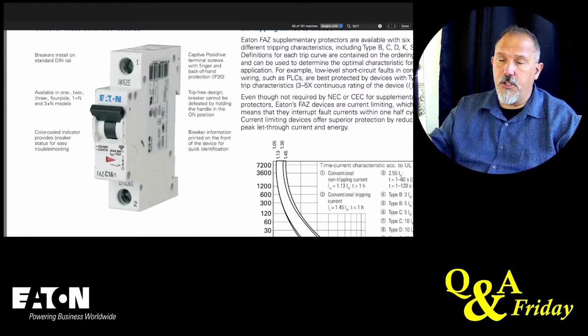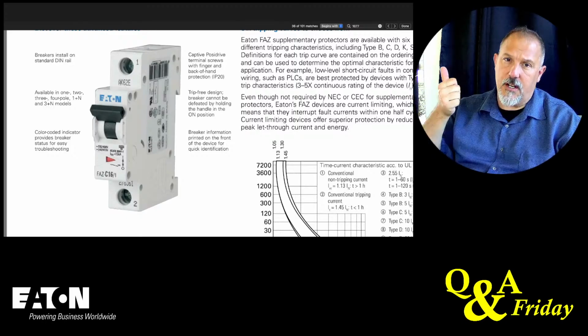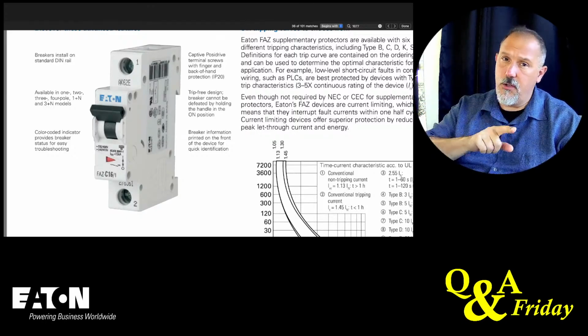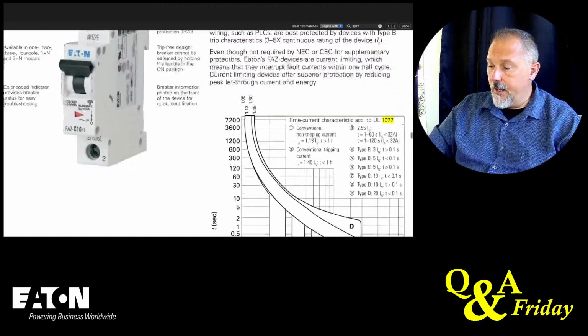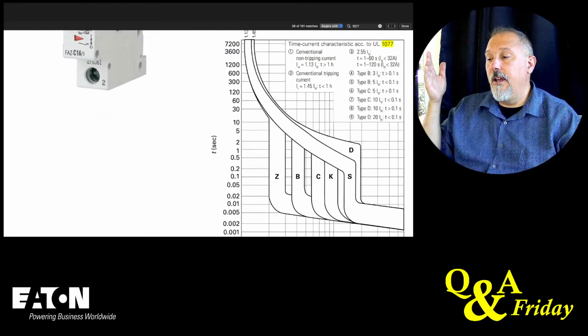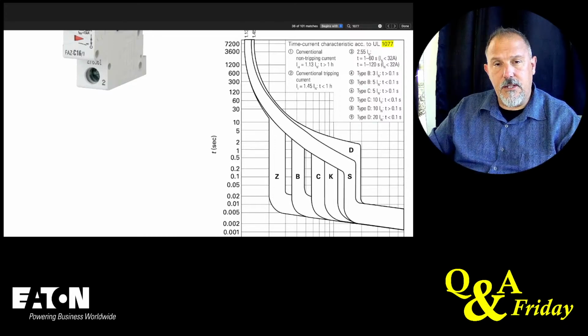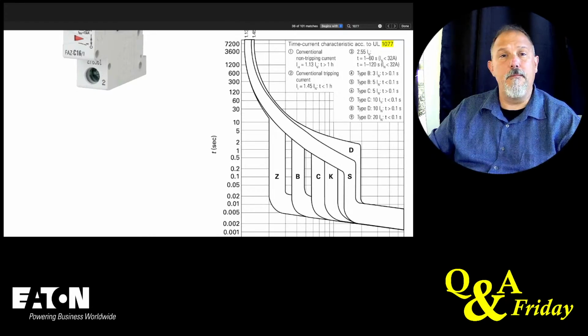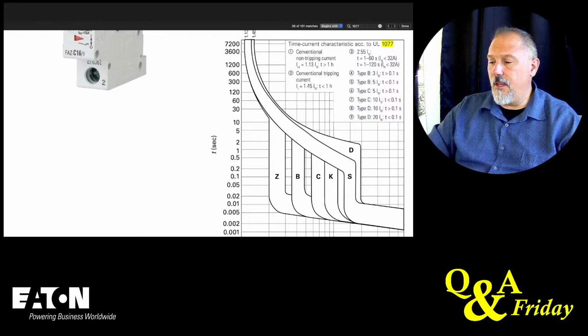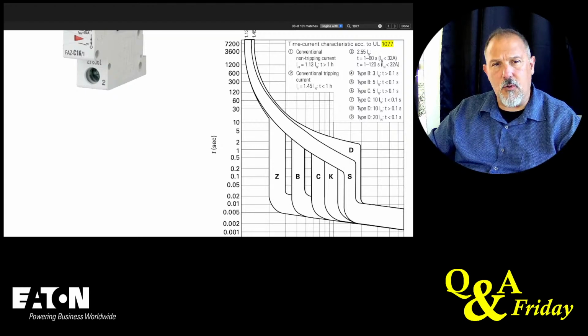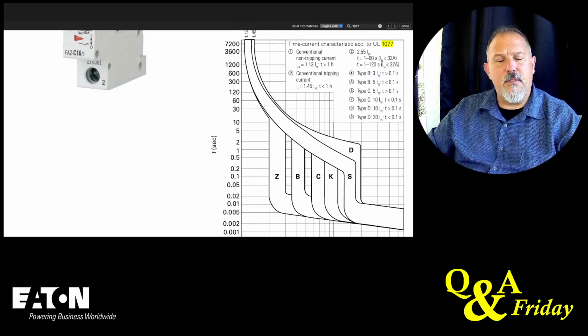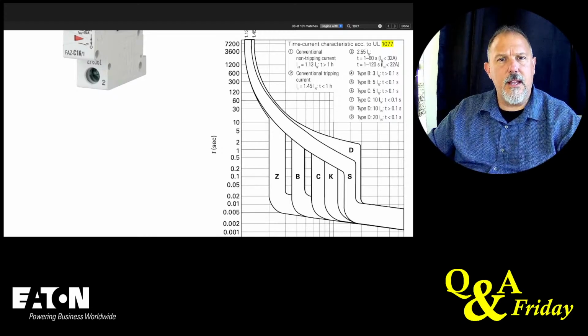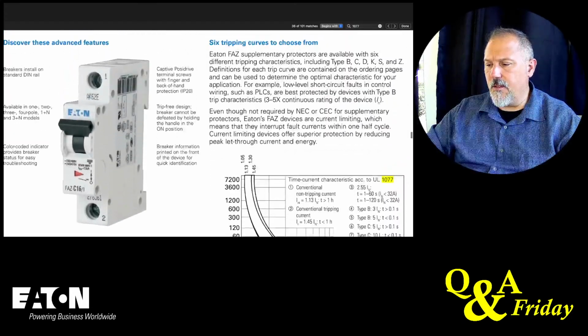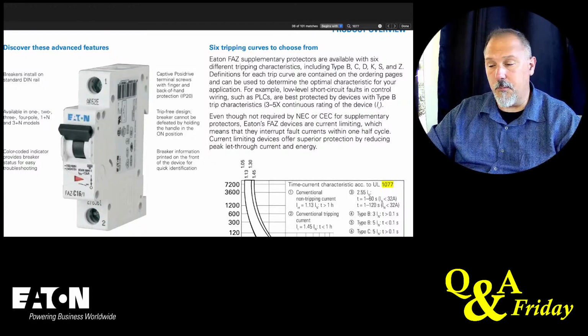Now, if I scroll back up in this document, you'll see a device that looks exactly like this, but it's UL 489, not a 1077. And to answer the specific question, it does have a thermal and it does have an instantaneous. They're just like a regular circuit breaker, but these are listed in such a way that they need a big brother to help them. They're not going to be a branch circuit overcurrent protective device. These are going to be found in industrial control panels and other similar equipment that we already talked about. They can provide local things to turn on and off. They do provide a level of protection, but again, not there to meet National Electrical Code requirements with regard to branch circuit.